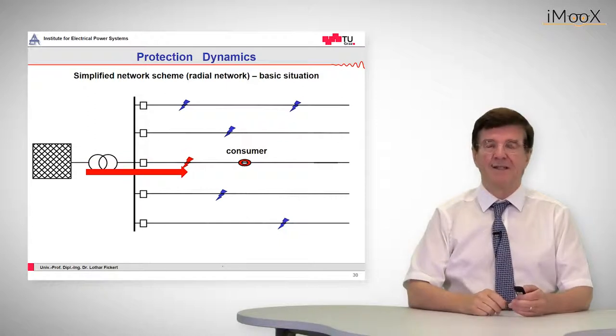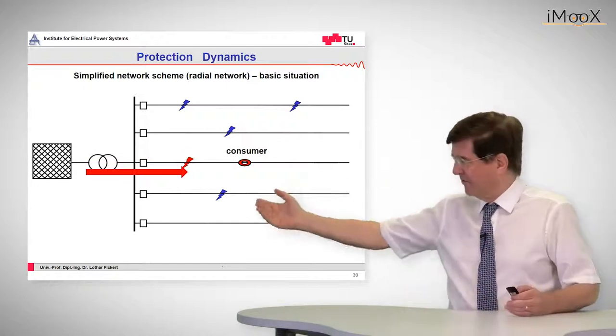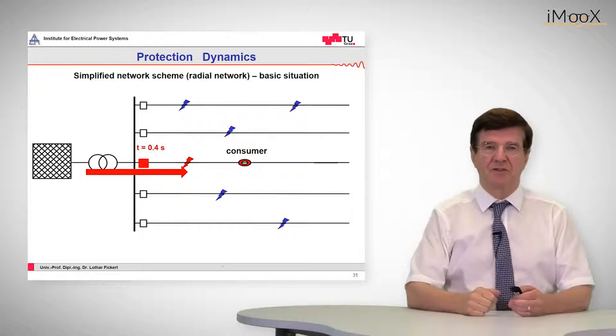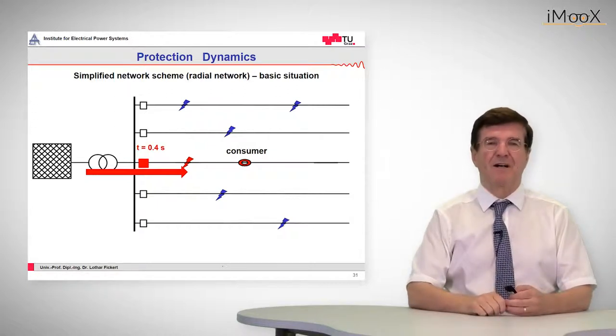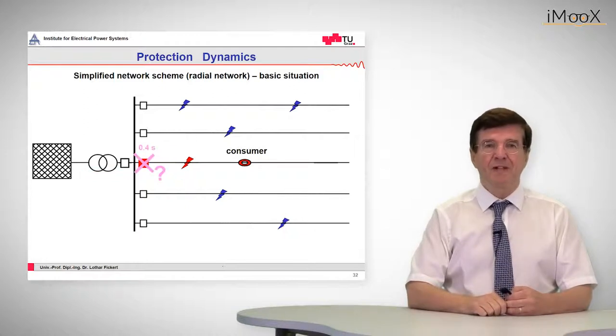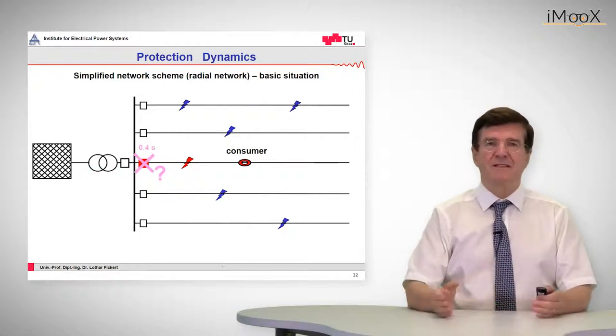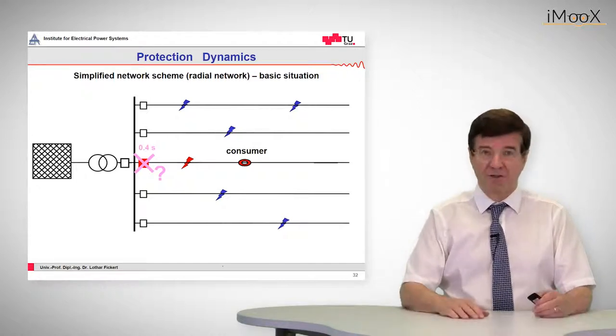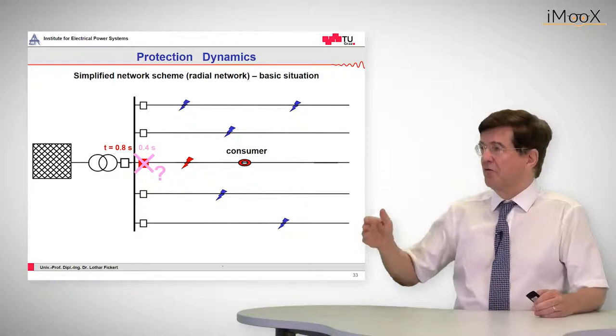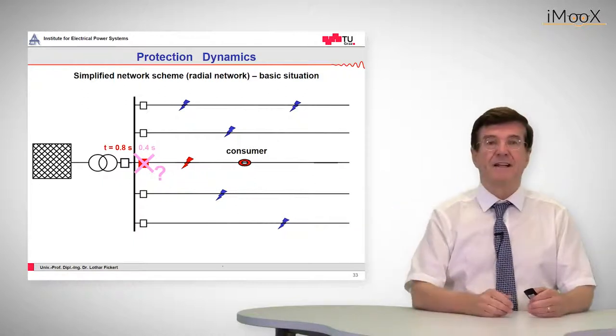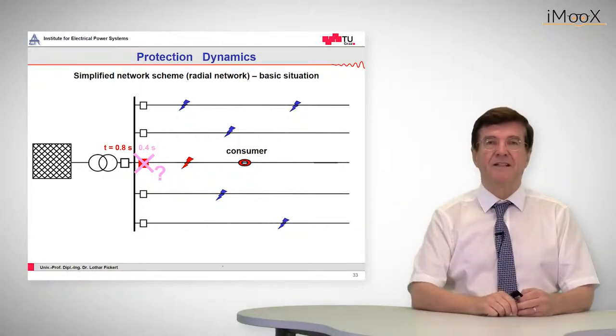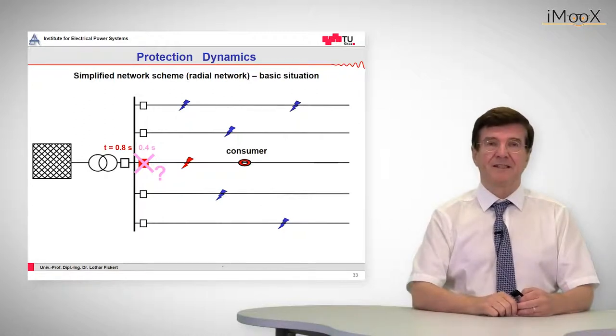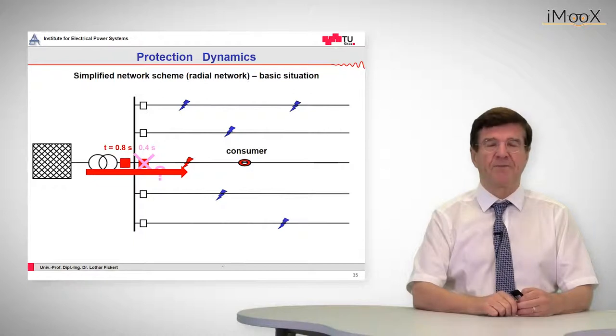Now a short circuit comes in and the short circuit current is flowing from the source to the fault and the relay will pick up after example 0.4 seconds. Now what happens if for whatever reason the trip does not occur? That means after 0.4 seconds the current keeps on flowing, flowing until, and now you see what has been inserted, another upstream relay with a grading time of 0.8 seconds will pick up and interrupt the fault.